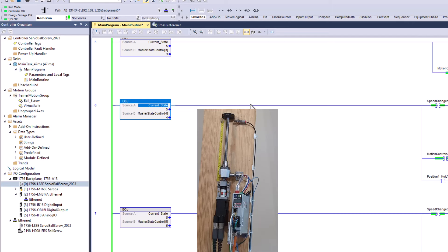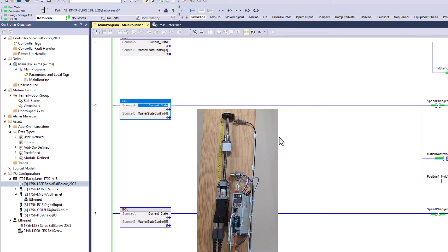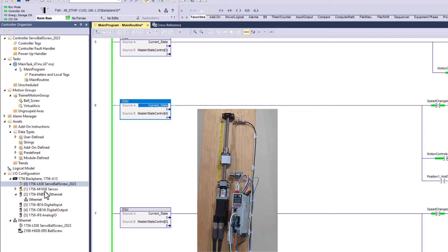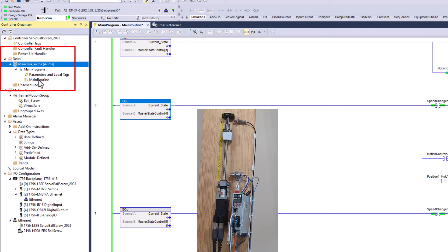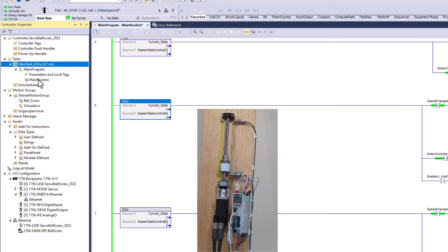Plus how I have my actual communication set up for the RPIs inside of my I/O configuration. You have to understand there's a lot of things that come into play. Your task rate, how often are you going to resample. You can't resample faster than your actual RPIs of your I/O configuration. If you do, you're asking for problems because you're trying to use the data before you can interpret the data. All of my RPIs generally are set to 20 or below so I can get my information as fast as possible. There are rare instances in process controls where I use 50, but then I take my periodic task up to 75 milliseconds. My periodic task in this case is 47, so my I/O communication RPIs are set to 20 so that I'm getting two times the data before I'm trying to control it.